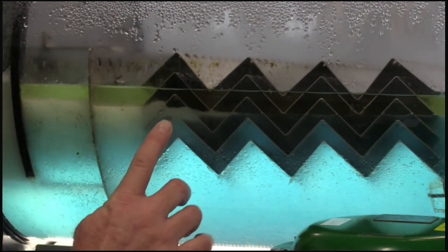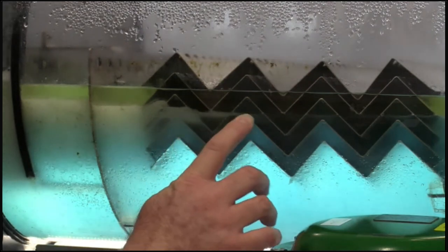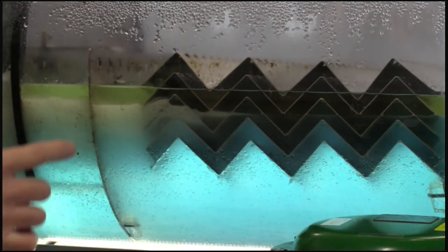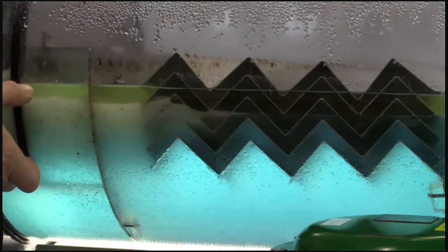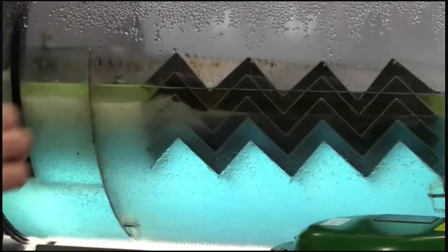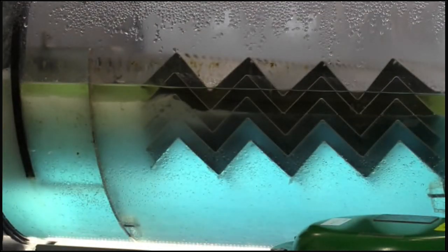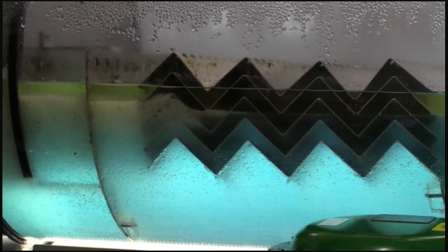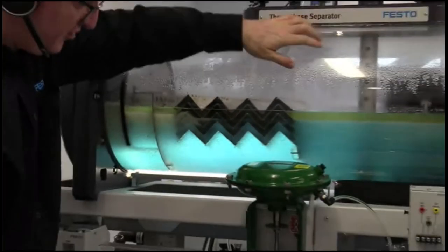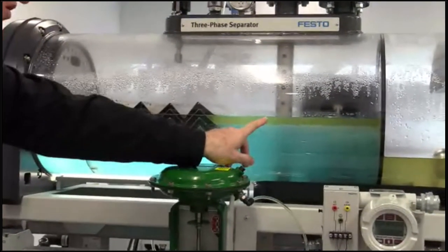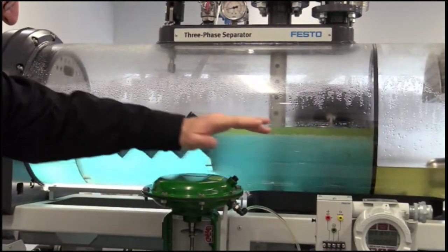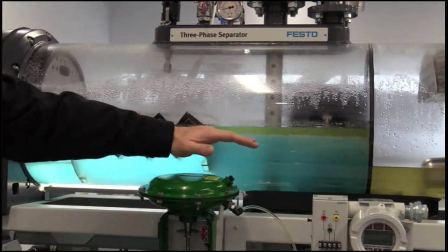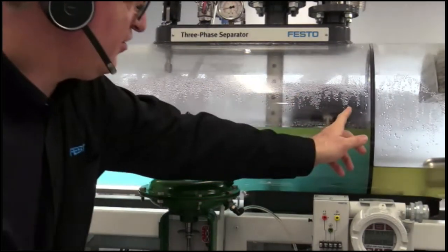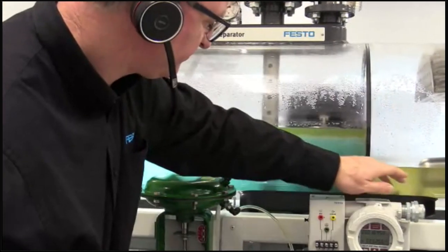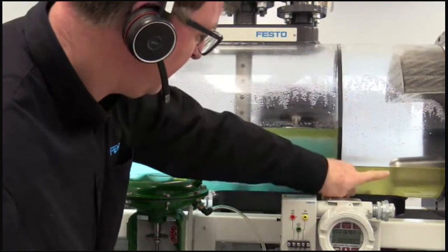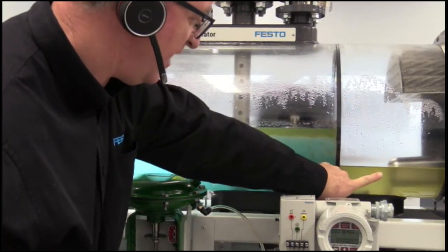So now we can see here how it is getting separated. So if we see it here, we have a lot of emulsion. And here, basically, we have already our three elements. So our instruments, the radar, is going to be measuring how much water and how much oil we have, because the oil is going to be floating over the water and is going to drop down this little wall here and get collected in this area.